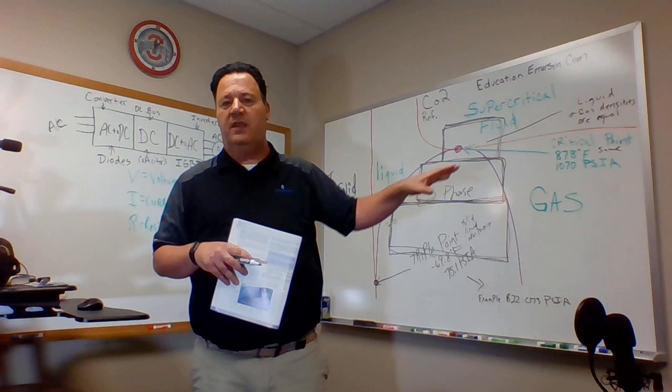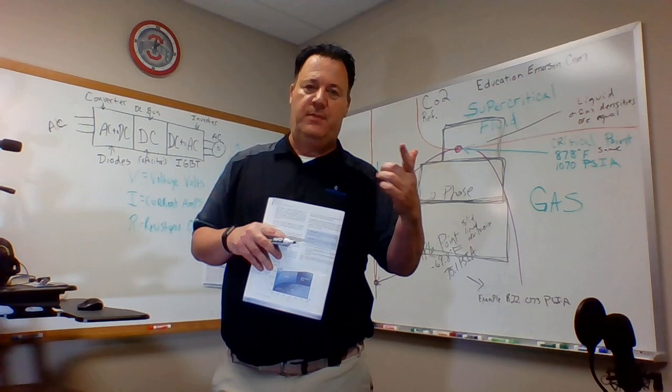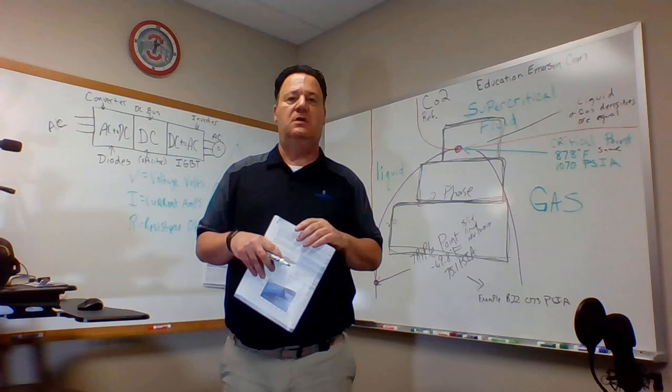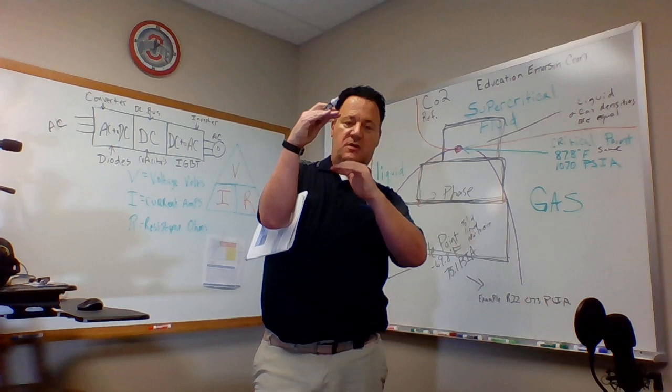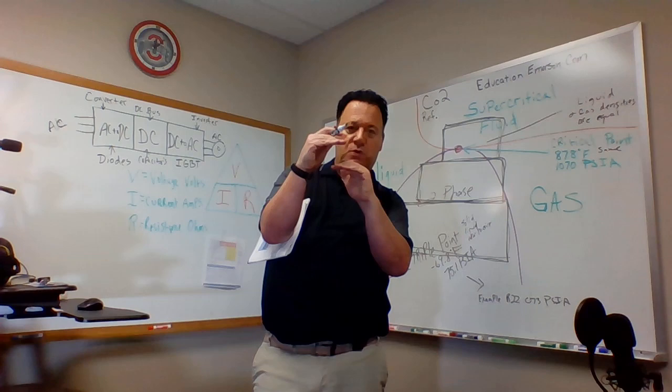Make no mistake about it, CO2 is very earth friendly, very, very good for the environment. All natural refrigerants are, ammonia, propane, what have you. But don't think it's just about the environment. For example, with HFCs, low temperature, an average or somewhere thereabouts on the compression ratio is 10 to 1. Remember, discharge pressure up here, suction pressure down here. The farther apart those numbers, the less efficient a compressor is. In comparison to CO2, a low temperature compression ratio is 2 to 1. So those numbers are closer, which makes it much more efficient.